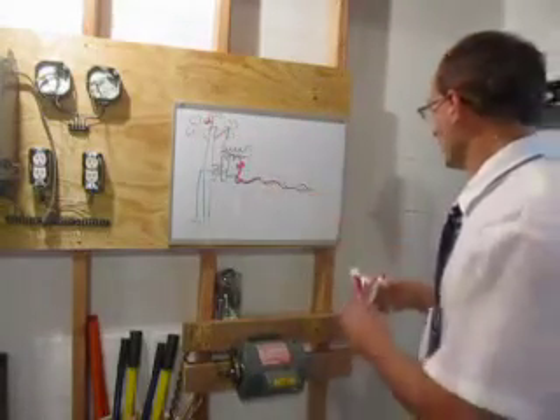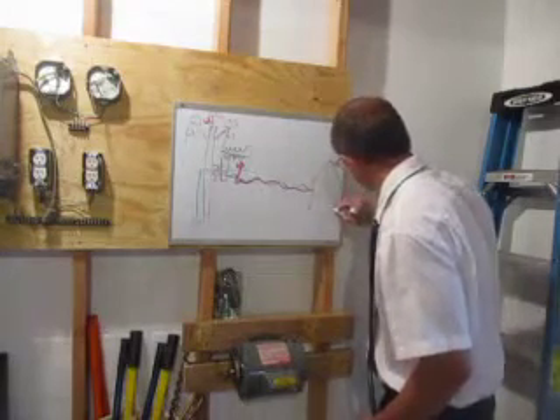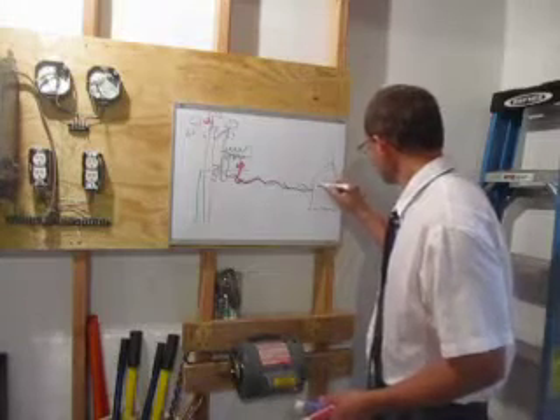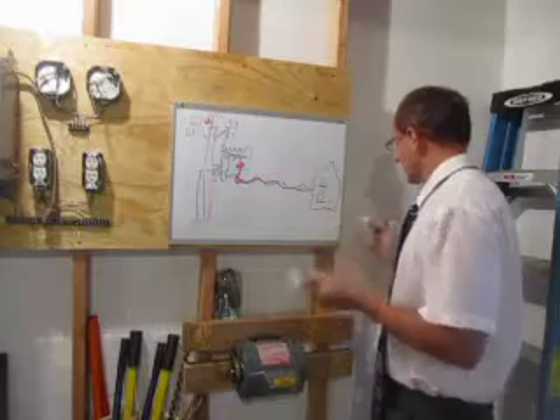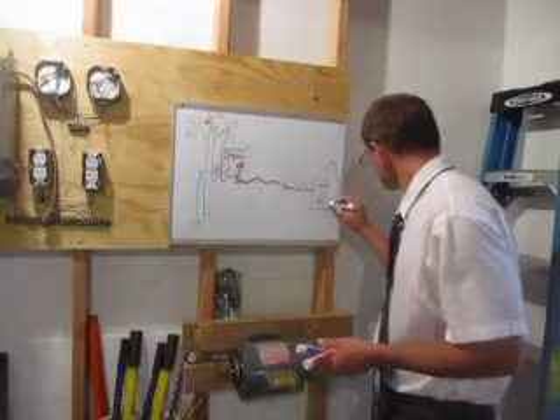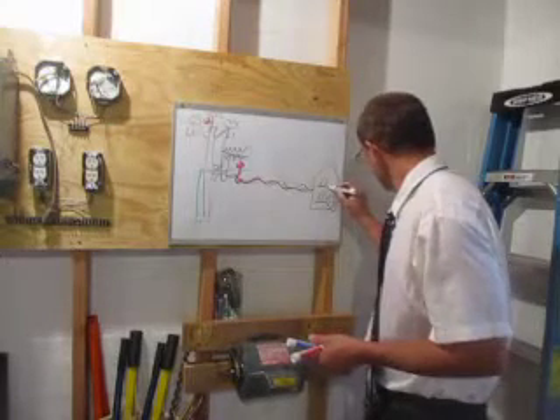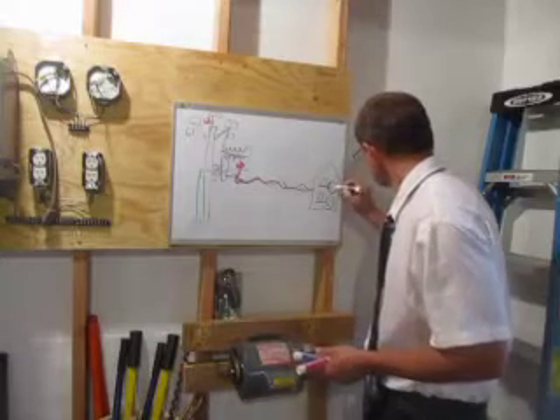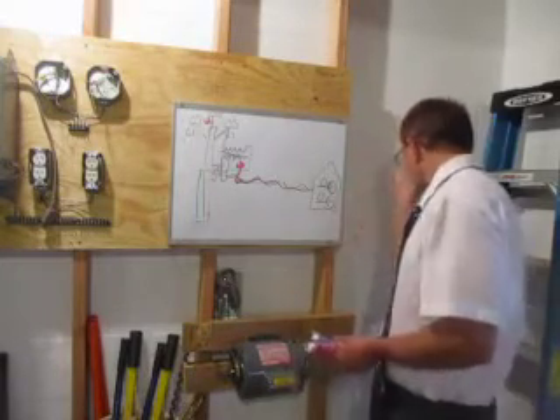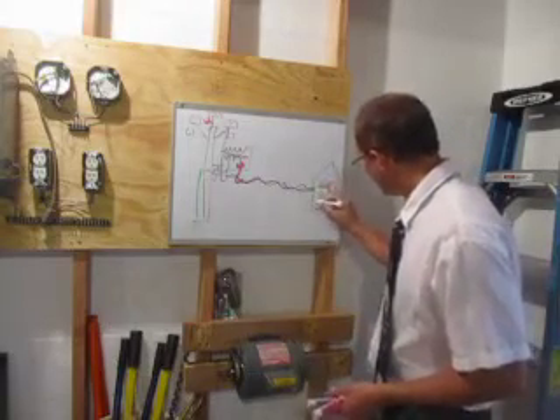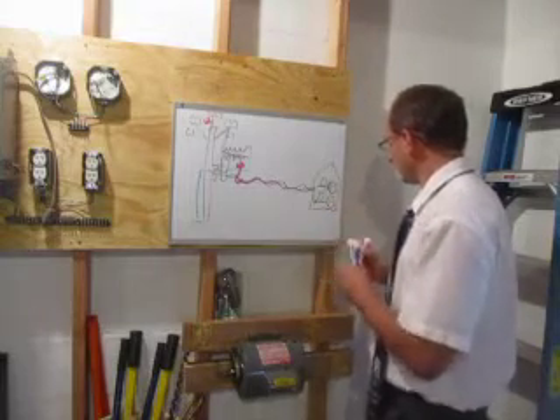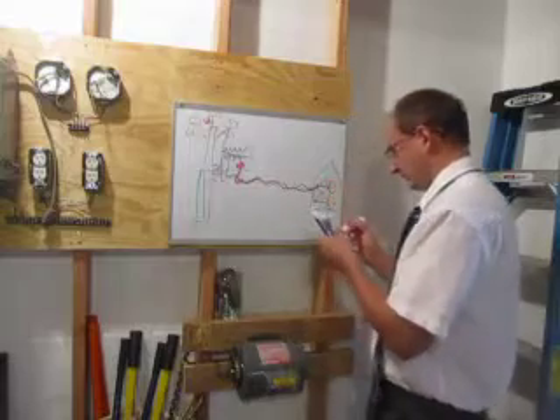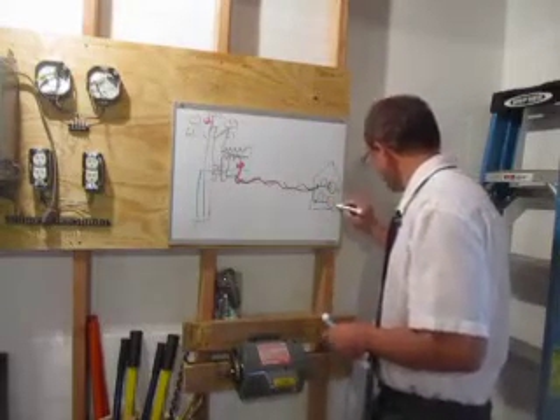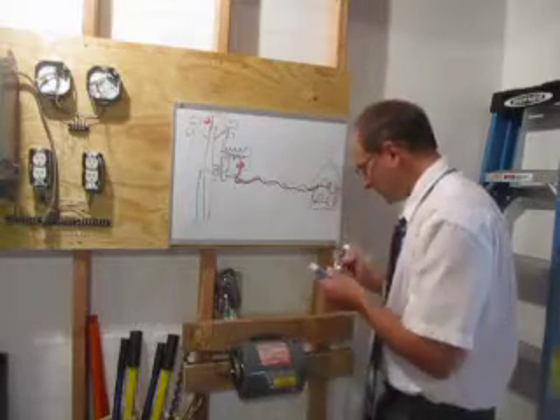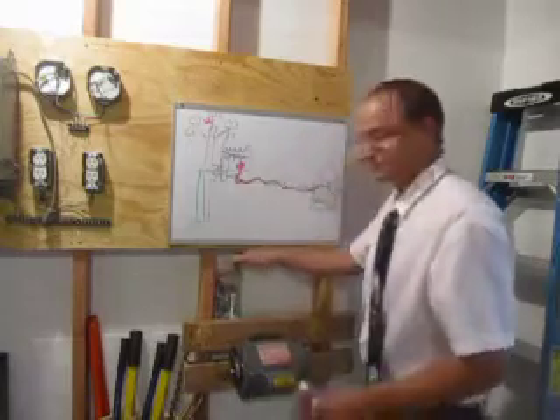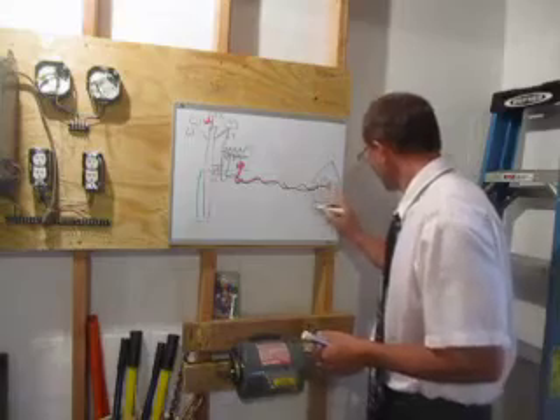So you got your 120/240 going to a house, goes to a house like this. Basically, you'd have a lighting circuit, and you'd have your plug, let's say. Small part of the plug is the live part, and that part's the ground conductor. So basically, your L1 will go half a circuit, join there. L2 will go there, half a circuit. And then next to that, half a circuit. And then this half a circuit goes to the ground conductor. Your ground conductor, green, comes in here like this, and it connects to this half.